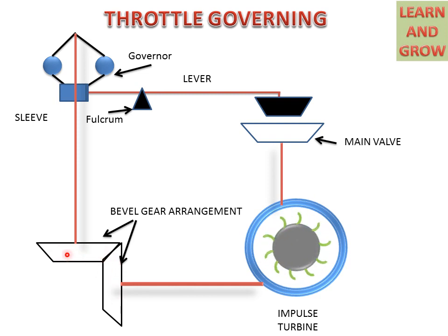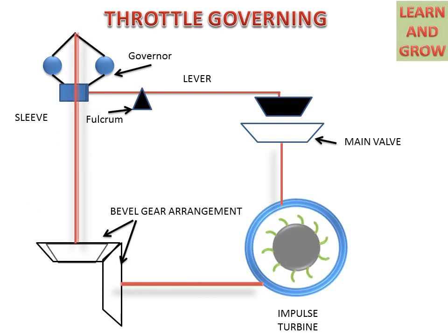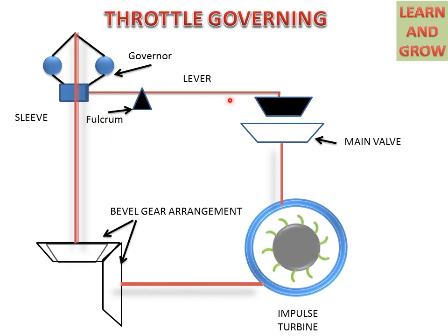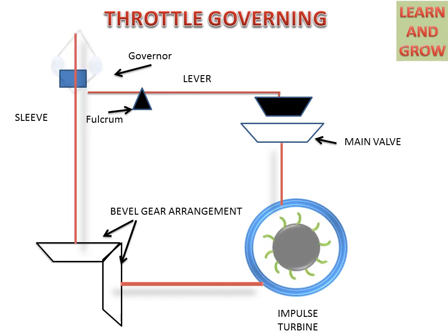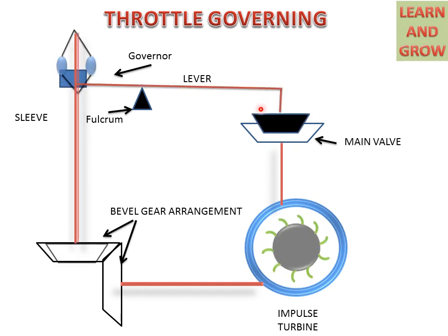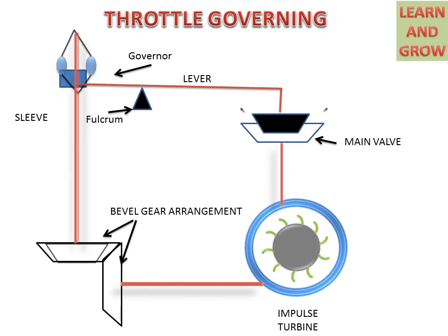This gear arrangement is connected to the governor. By the rotation of the rotor, the governor will also start rotating at higher speed. At higher speed, the governor fly balls will go in the upward direction and the sleeve will also go upward, pushing the valve in the downward direction to restrict the flow. So this valve restricts the flow of water to the turbine, and in this way Throttle Governing maintains the flow of water.